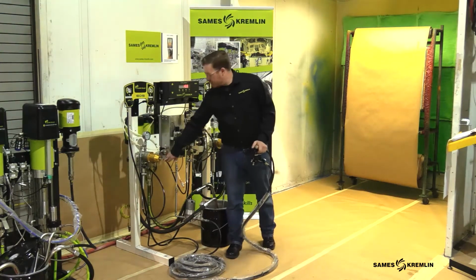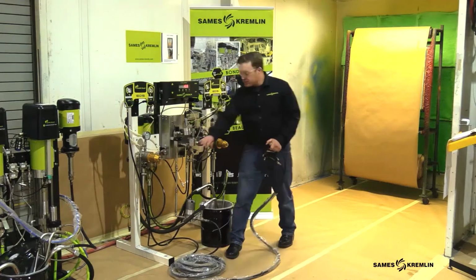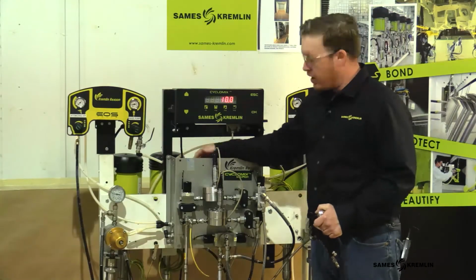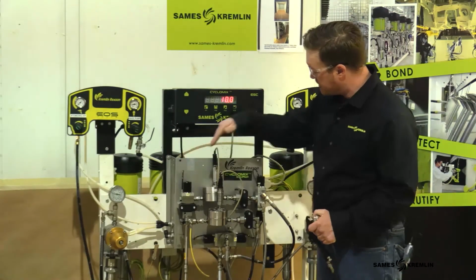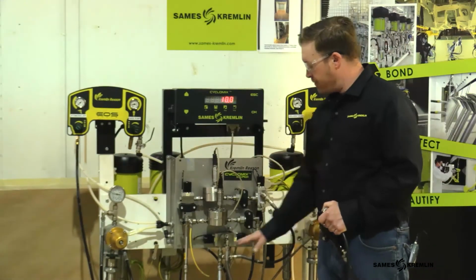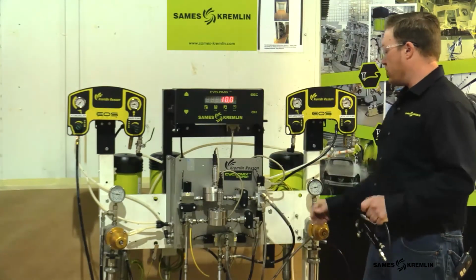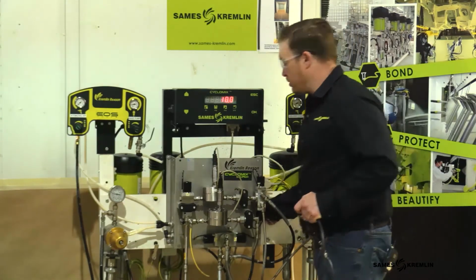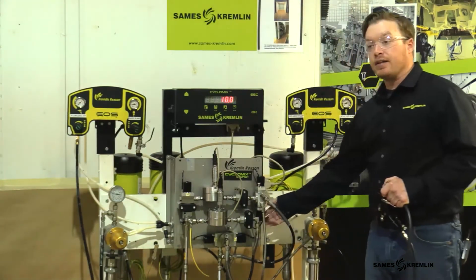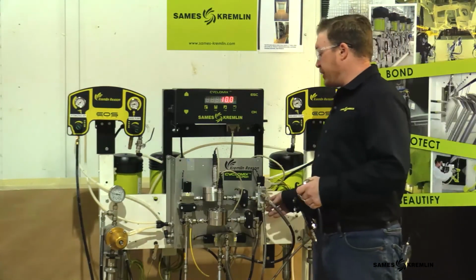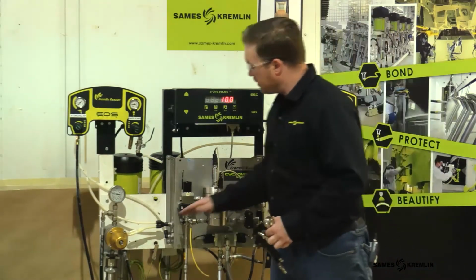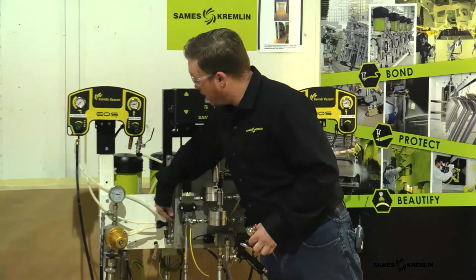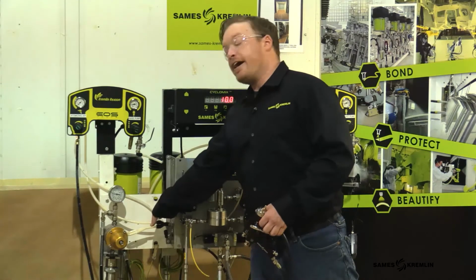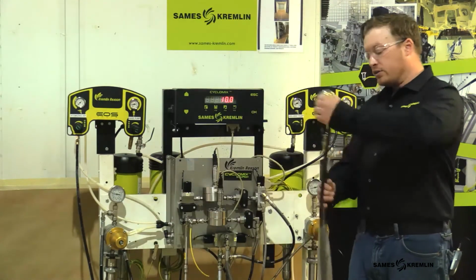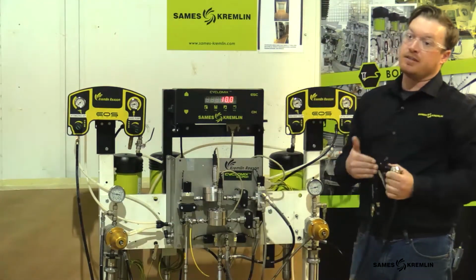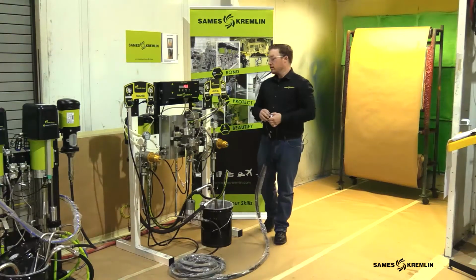And the way that it works is the air in is going to a series of solenoid valves to control the pilot signals for our valves. And it's also going to be going to this air flow switch on the side of the controller. That air flow switch is then tied in to R2. And the R2, again, is air outlet. And that air outlet is set up to be our atomizing air to our spray gun.